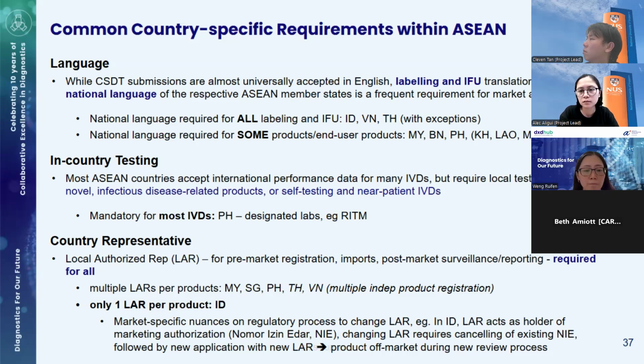And another key stakeholder for market registration in the region really is this concept of the local authorized representative. The local rep is actually required by all ASEAN countries for pre-market registration as well as imports and post-market surveillance. While most countries accept multiple local reps, in Indonesia, which is one of the countries of interest, actually only one local rep is allowed for any product at any point in time.